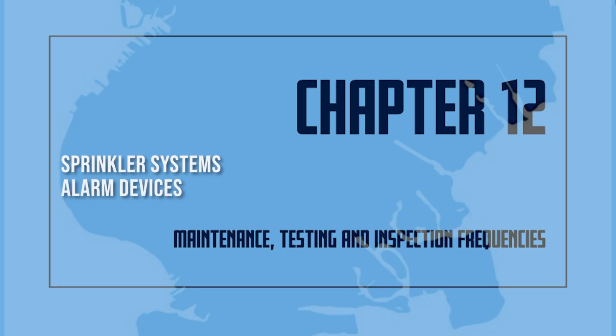maintained. Alarm devices. Alarm devices shall be inspected quarterly to verify that they are free of physical damage. Hydraulic nameplate. Hydraulically designed systems shall be inspected quarterly to ensure that it is attached securely to the sprinkler riser or sprinkler control valve and is legible.